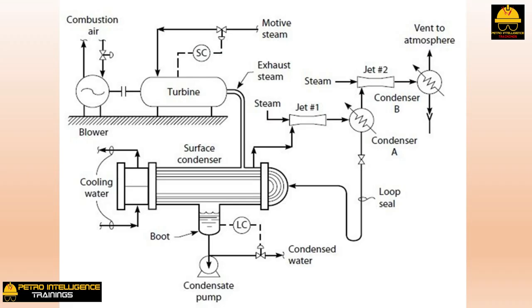In the lecture on steam turbines, several problems pertaining to steam jet pre-condenser and inter-condenser problems were reviewed. Surface condensers serving condensing steam turbines are subject to all the same problems and more. A standard surface condenser package with an associated two-stage jet system is shown. I will relate one engineer's trials and tribulations with K805, an auxiliary combustion air blower at the refinery. The problem with this new air blower was that they could not bring the turbine speed above its natural harmonic critical speed, which is stamped on the manufacturer's nameplate.